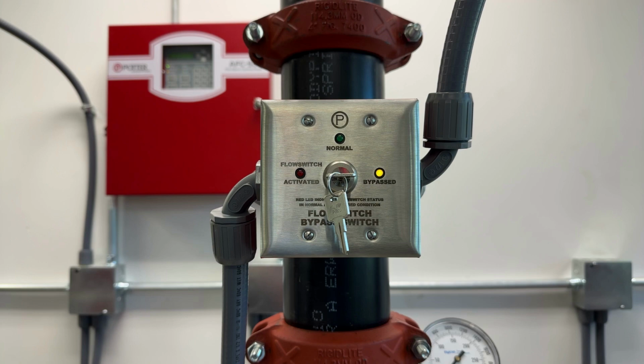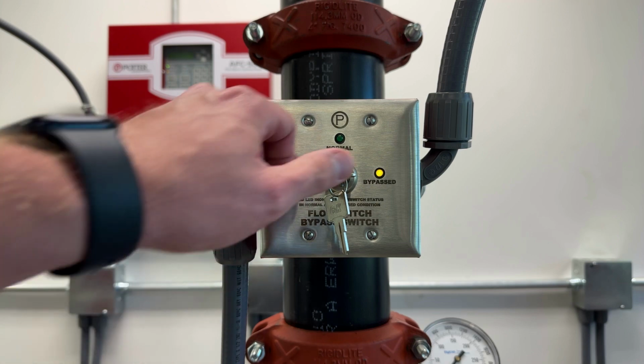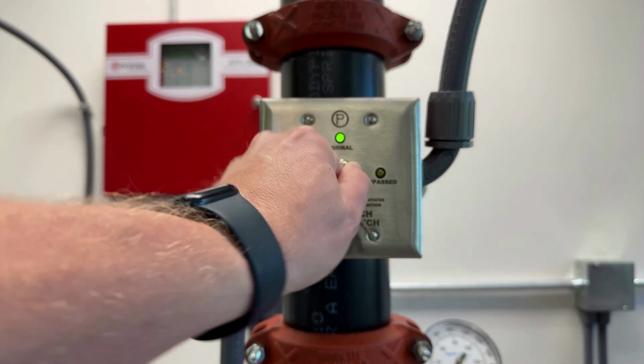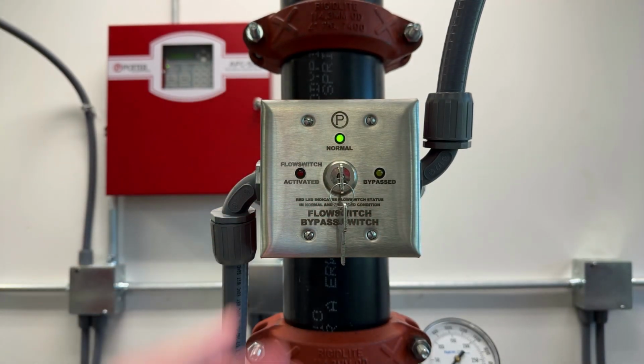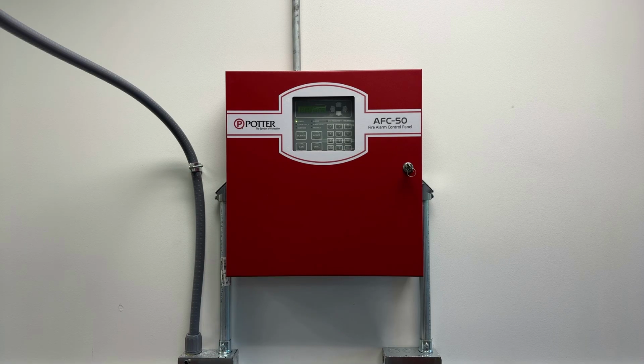Once the maintenance has been completed and the sprinkler system has been filled and restored back to normal operation, turn the key on the flow switch bypass switch to the normal position and then remove it to prevent tampering. You may need to reset the fire alarm control panel if the trouble is latching in order to return it to normal.